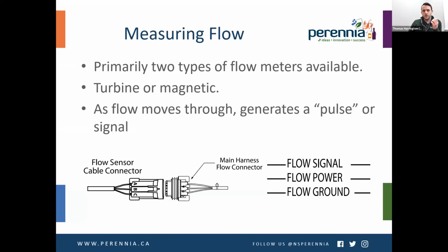For measuring flow, there's primarily two types of flow meters available: a turbine or a magnetic type sensor. Similar to the speed sensors, as flow moves through these, it generates a pulse or a signal. This is just like a common wiring diagram that you might see on a typical flow meter. So you're going to have power, ground, and then your signal, which is going to be your pulse that's generated as the flow meter turns.